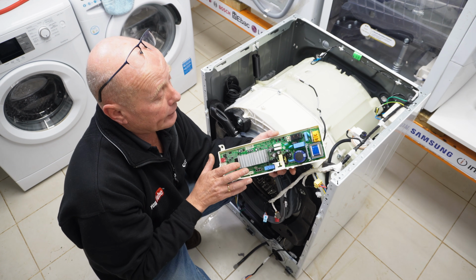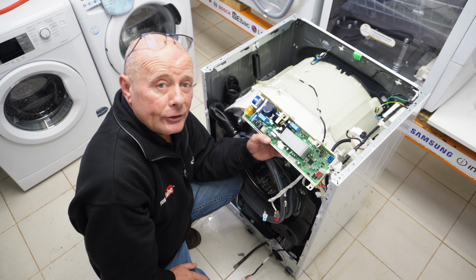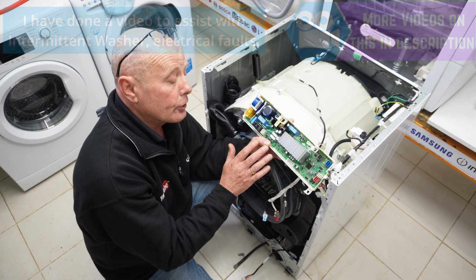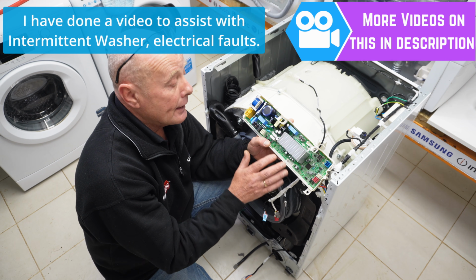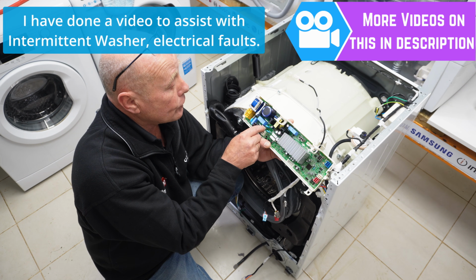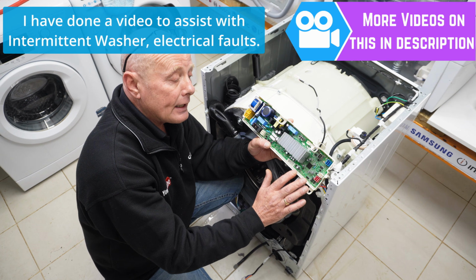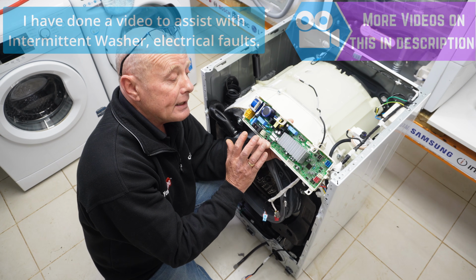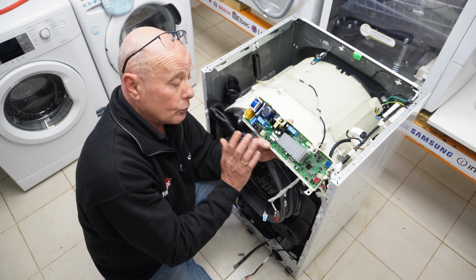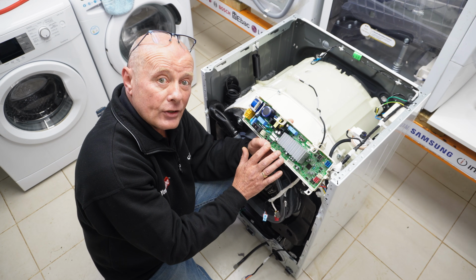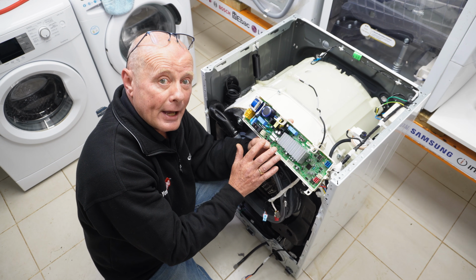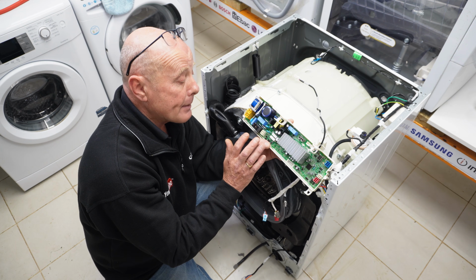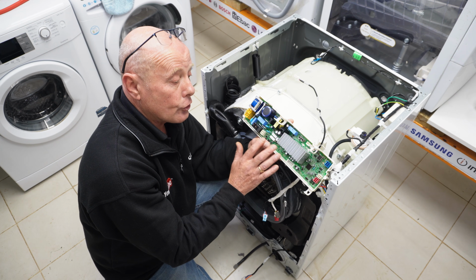Okay, let me explain a few things about the circuit board while I'm here. Intermittent faults can be down to the circuit board, or power failures can be down to the board as well, and other faults as well. There are a couple of fuses on these circuit boards which you can see here and here, but the problem being is they've encapsulated the whole circuit board in a silicon, and this is because it is designed to be moisture resistant. In some ways it's very good, in other ways it's very bad, because it's very difficult to repair the circuit boards, and for the amount of work that's involved, sometimes it's just not worth it.